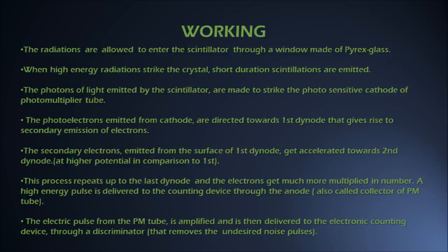Now let us come to the working of a scintillation counter. The window made of pyrex glass allows the radiations to enter the scintillation counter. When high energy radiations strike the crystal inside the scintillator, short duration scintillations — that is, flashes of light — are emitted by the crystal. The photons of light emitted by the scintillator are then made to strike the cathode of the photomultiplier tube through an optical coupling, which is made of a special fluid.